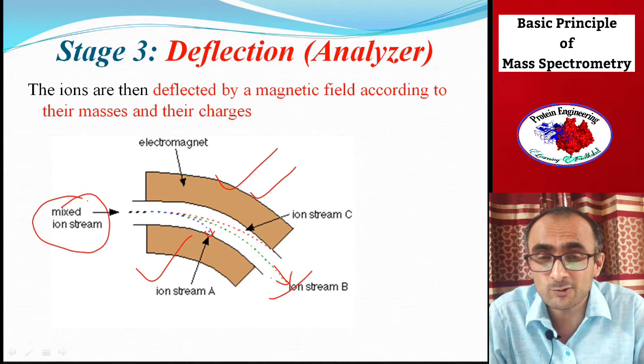So in a typical magnetic sector analyzer, you have a magnetic field which deflects all the beams depending on their M by Z. If the ion is lighter, it will have maximum deflection. A heavier ion will have the least deflection. So that's how this beam is then focused into a detector which can collect the beam. At a given magnetic field, you can collect only one type of M by Z containing beam. If you want to collect the rest of the beams, then you need to change the magnetic field.